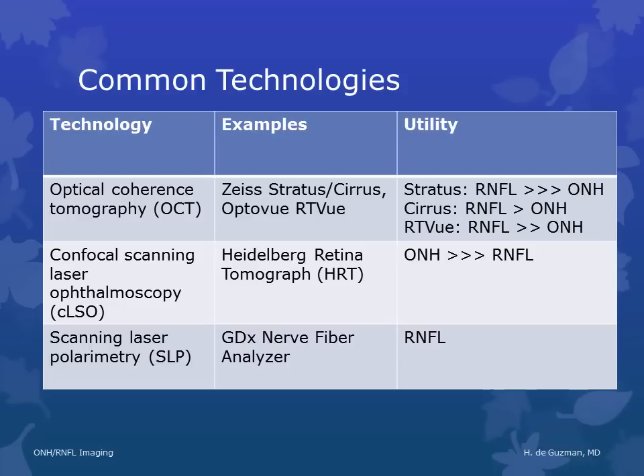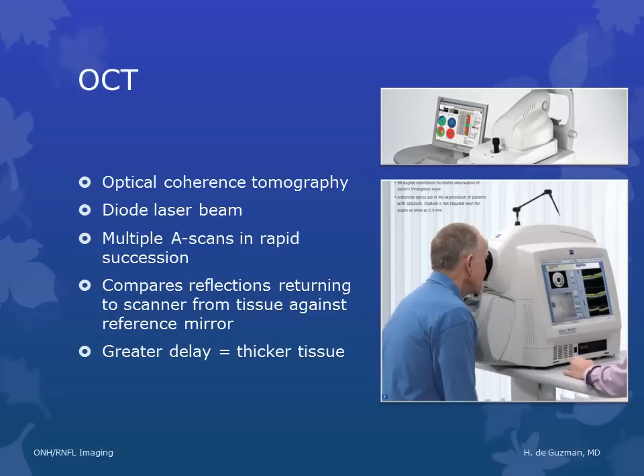This lecture will be mostly about the OCT because that's the most common machine locally. OCT uses a diode laser light source and it performs multiple A scans in rapid succession. It compares the reflections of the light returning to the scanner from the sample or the tissue against reflections returning from the reference mirror. When there's a greater delay in the reflection, that means that the tissue being examined is thicker. The photo above is the Stratus OCT and the photo below is the Cirrus OCT.